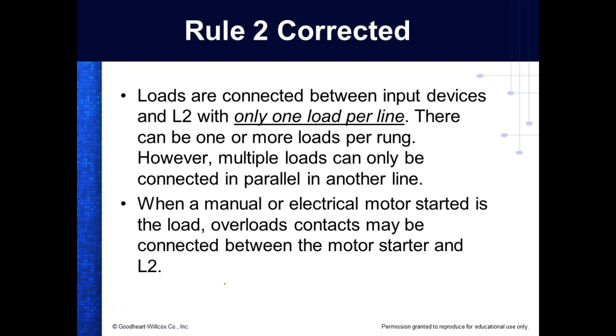If the overload is in the motor, and this is required by OSHA, that if a motor's over like half a horsepower, it has to have an overload. A lot of your single voltage motors, the overload will be in the motor. And if the overloads are in the motor, then you don't have to use a magnetic motor starter.